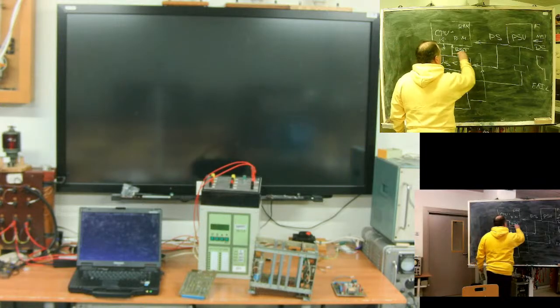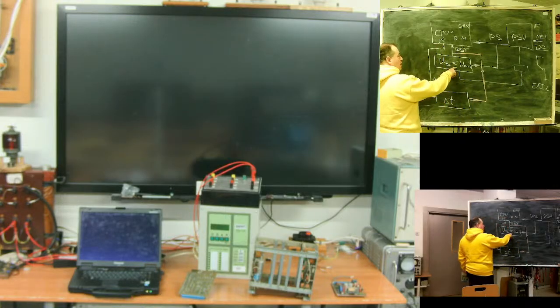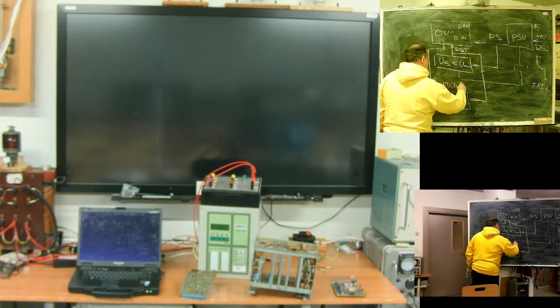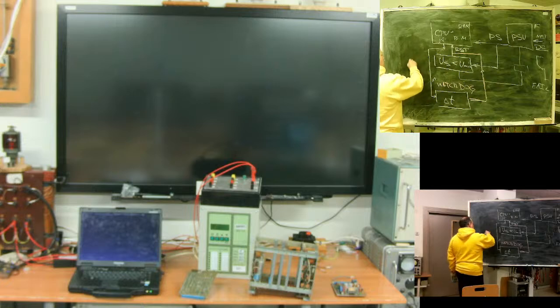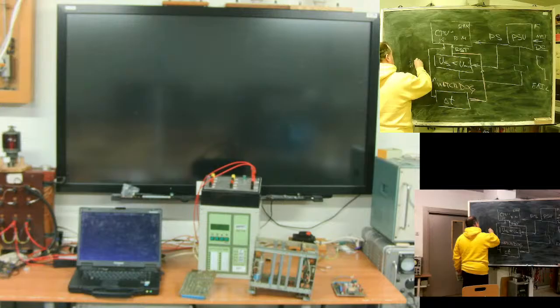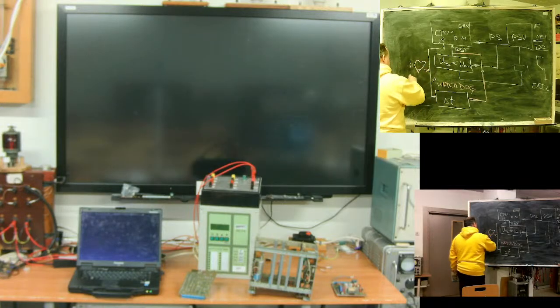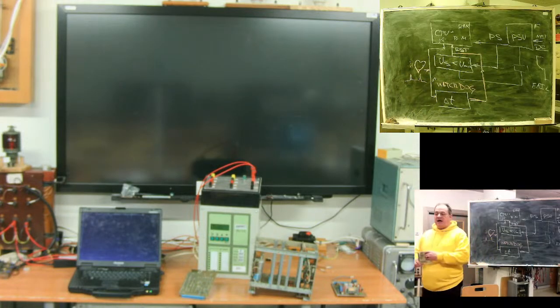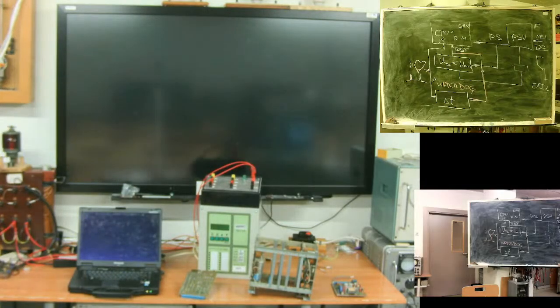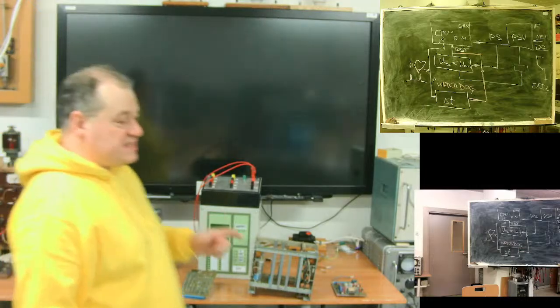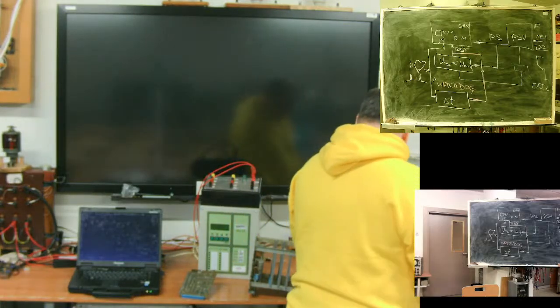I can draw it in red. So this one, power control watchdog. Okay. Who draws hearts like this? Heart pulse. Inside the program code, a special part is planted, so within the cycle a signal is sent to reset the watchdog timer. If the signal does not arrive, the system will get a hard reset. Good practice is to have an indication that a hard reset occurred. Good practice. Okay. Power supply, we'll speak later.